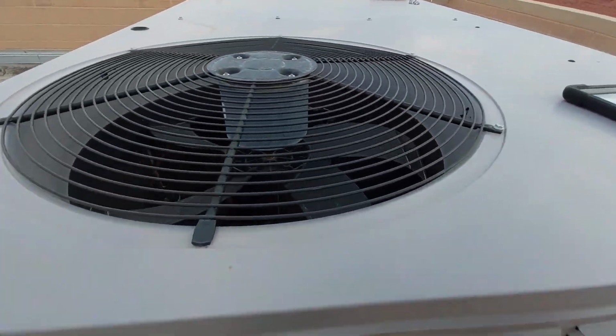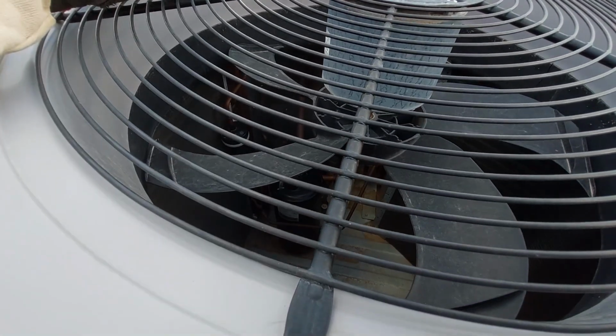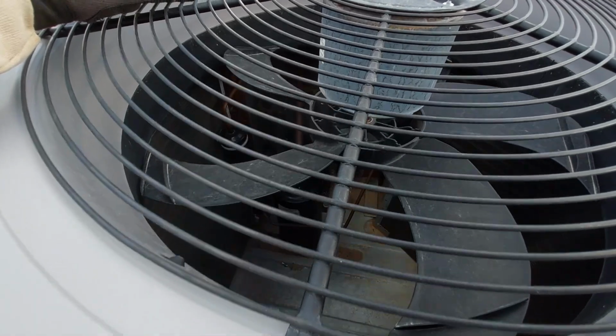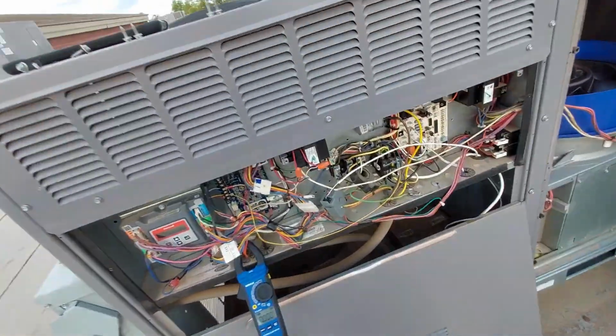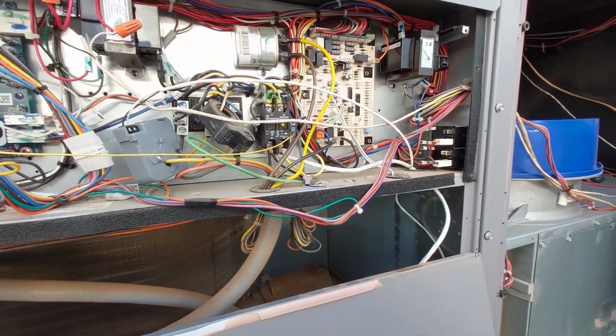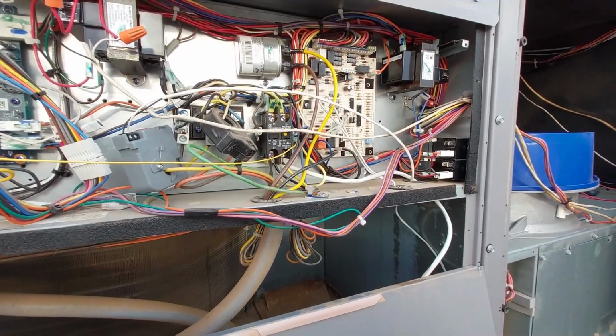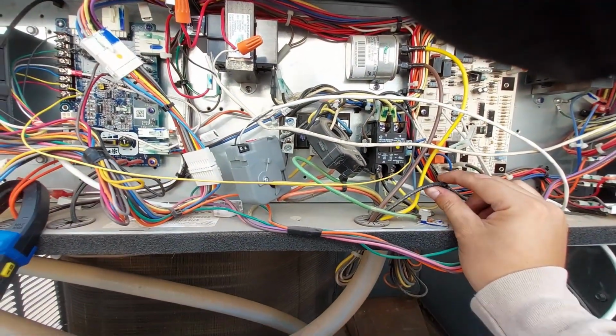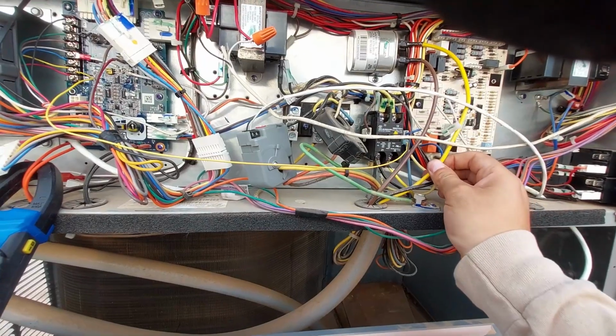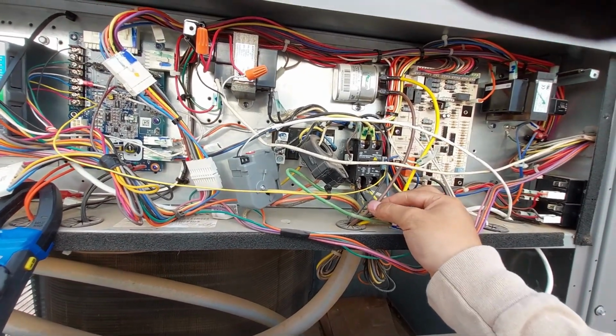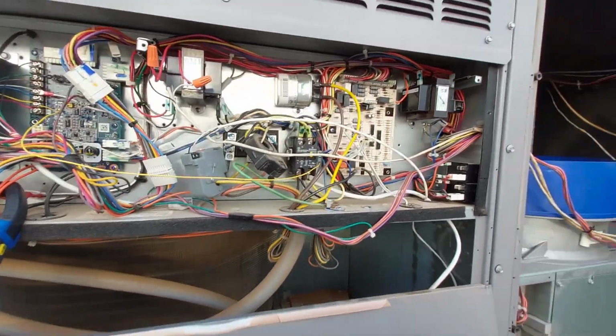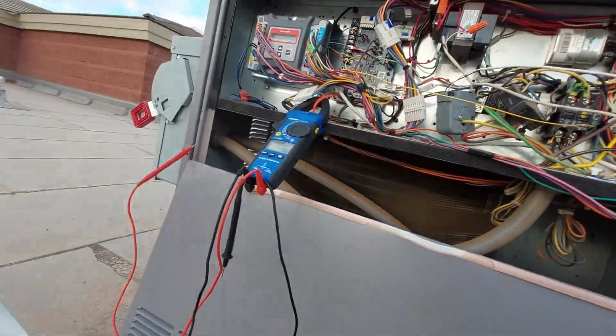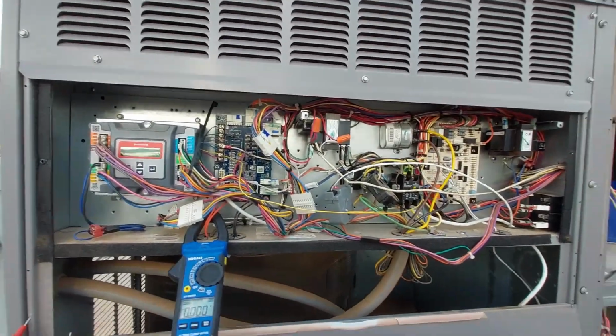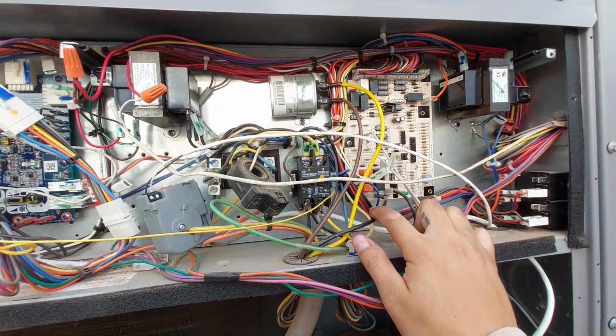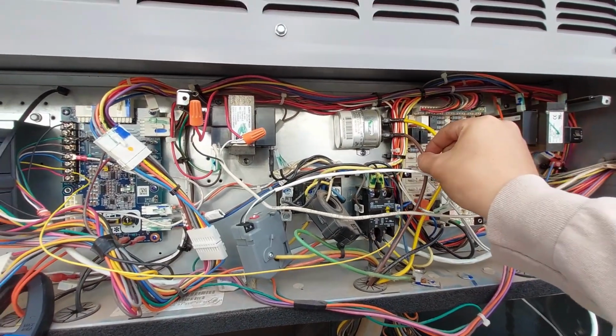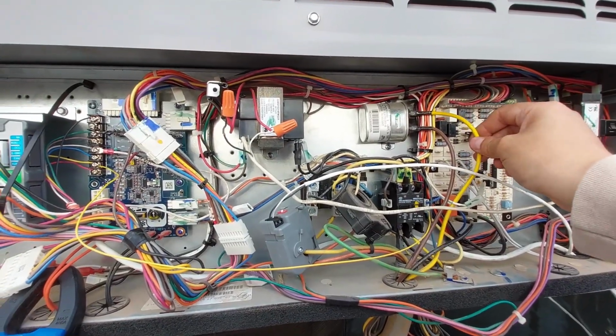So, yeah, I'm a little confused. How do I get that motor to run? Okay, so I'm getting 200 volts here. I should be getting 200 volts here as well. Alright, let me turn it back on. Let me take voltage and go from there. Alright, so I turned it on again. I checked voltage here at the black wire for my condenser fan motor. I'm getting 280. Then I checked it here on the brown. I'm getting 280 as well. Here on the yellow, I'm also getting 280.